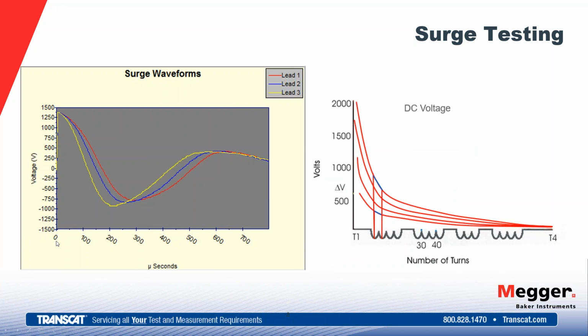Again, surge testing. This is a graph here of a surge test. We see the 3 leads, the red, blue, and yellow, of the 3 phases. And then as we pulse this motor, it rings back and forth between the winding under test and the ringing capacitor of the tester, and produces this type of waveform. What we're looking for as we raise voltage up is no change in that waveform. The amplitude will change, but we don't want to see any kind of shifting, which would be classified as an erratic waveform, shifting left or right.